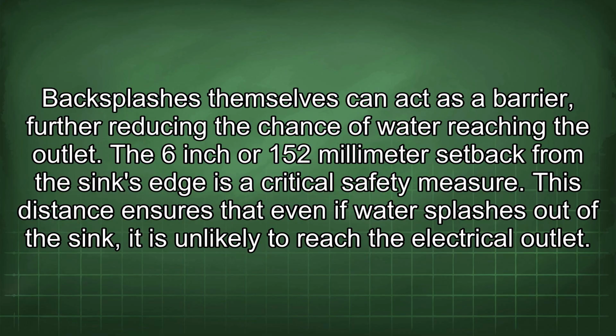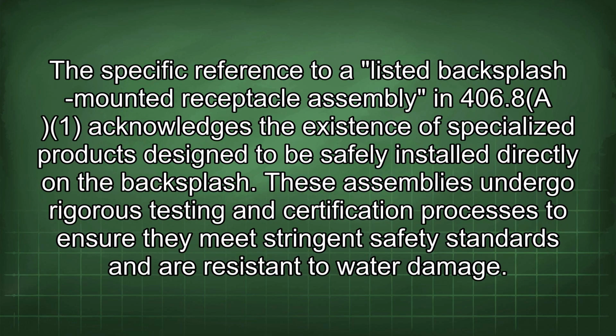The 6-inch or 152 mm setback from the sink's edge is a critical safety measure. This distance ensures that even if water splashes out of the sink, it is unlikely to reach the electrical outlet. The specific reference to a listed backsplash-mounted receptacle assembly in 406.8a acknowledges the existence of specialized products designed to be safely installed directly on the backsplash.